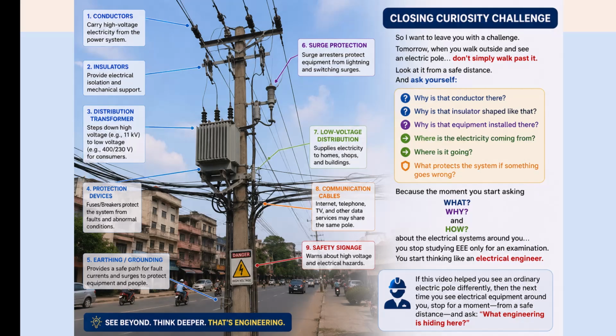You understand lightning and why surge protection is necessary. You can look for grounding and connect it with both electrical behavior and safety. You can recognize that not every cable on a utility pole necessarily carries electrical power. Most importantly, these are no longer separate ideas. They are connected. The conductors, insulators, transformer, protection, surge protection, grounding, and communication infrastructure all have different jobs, but they exist together in the same physical system.